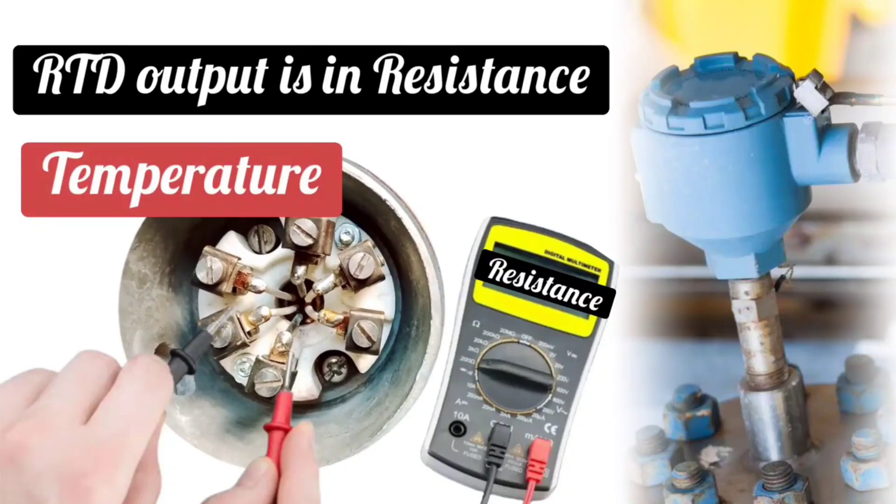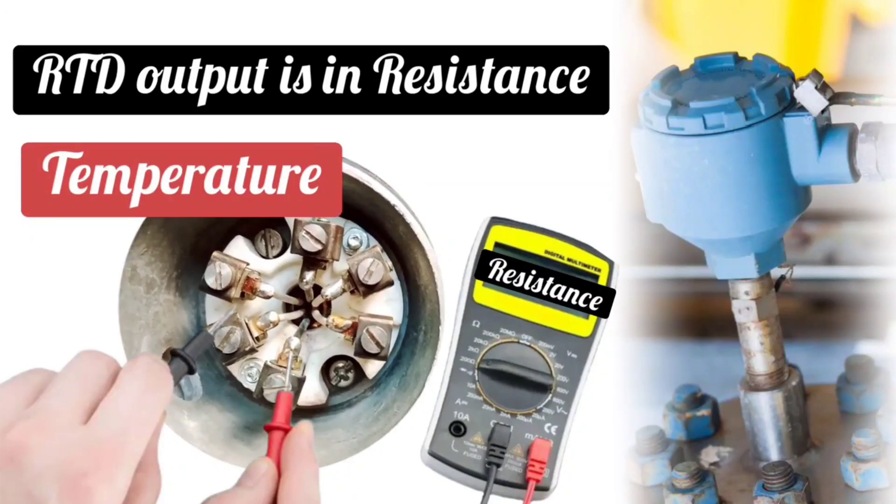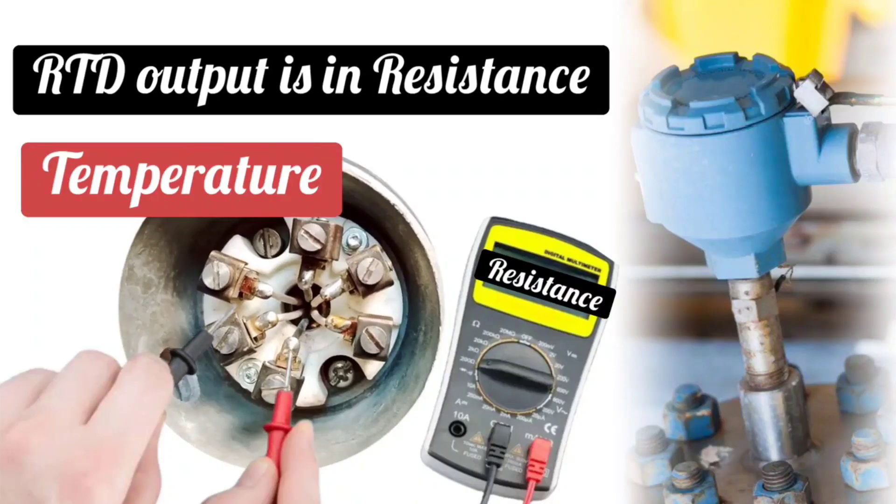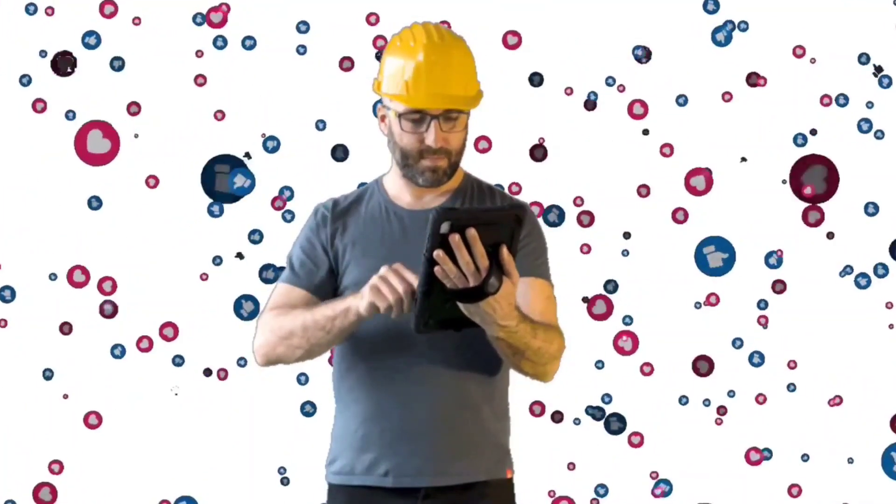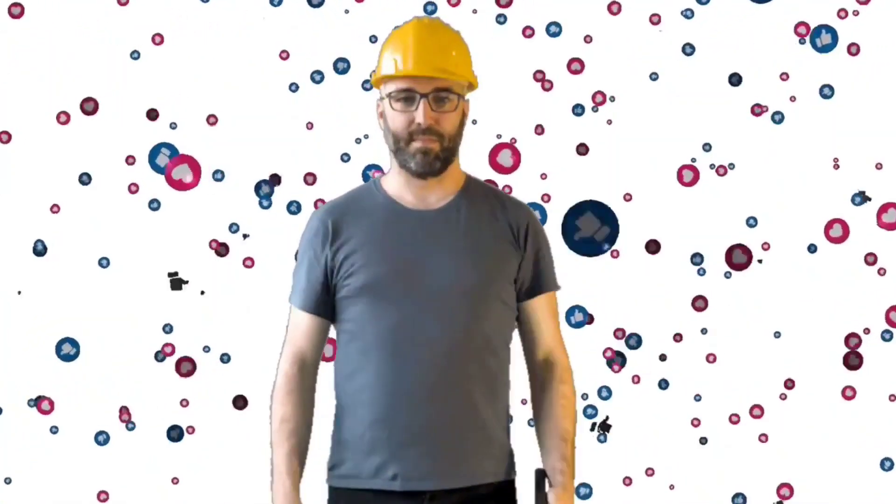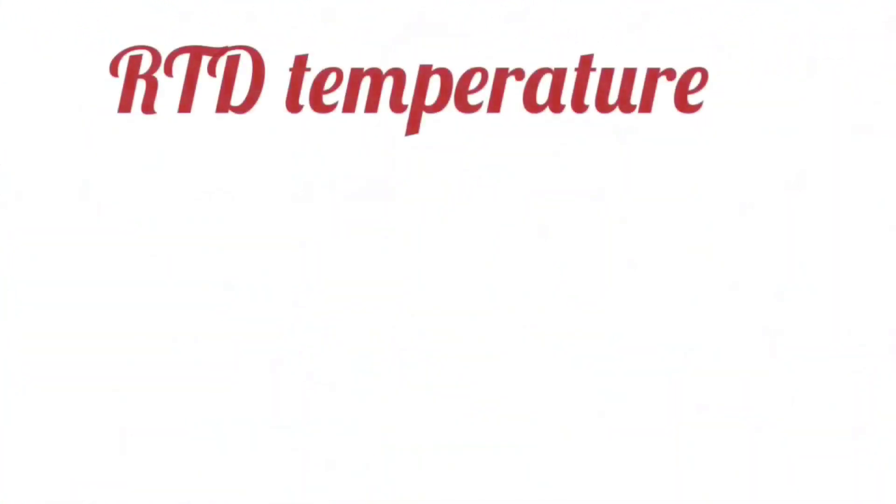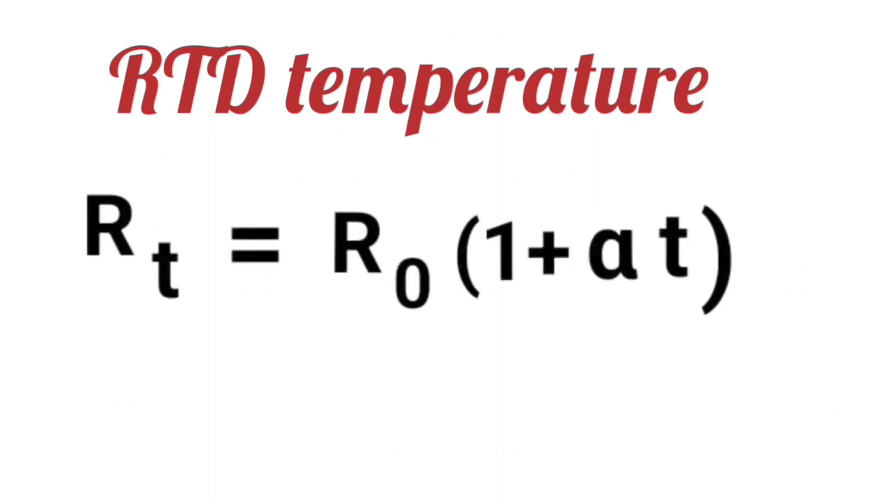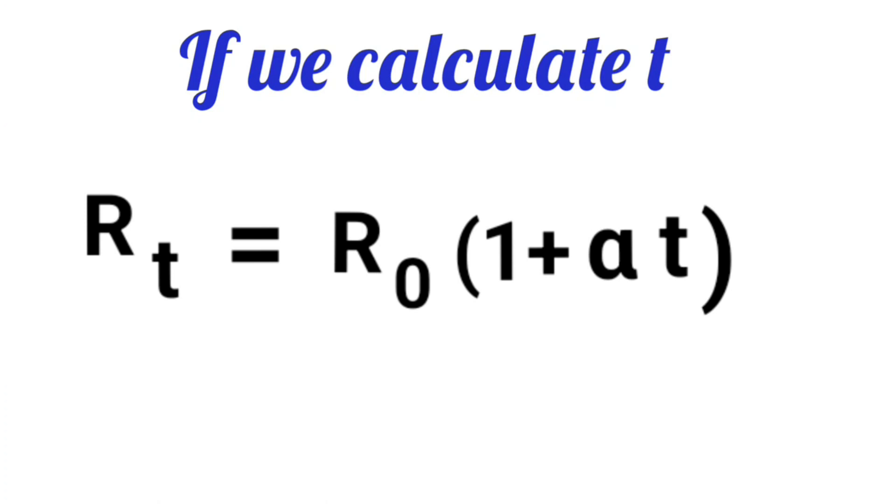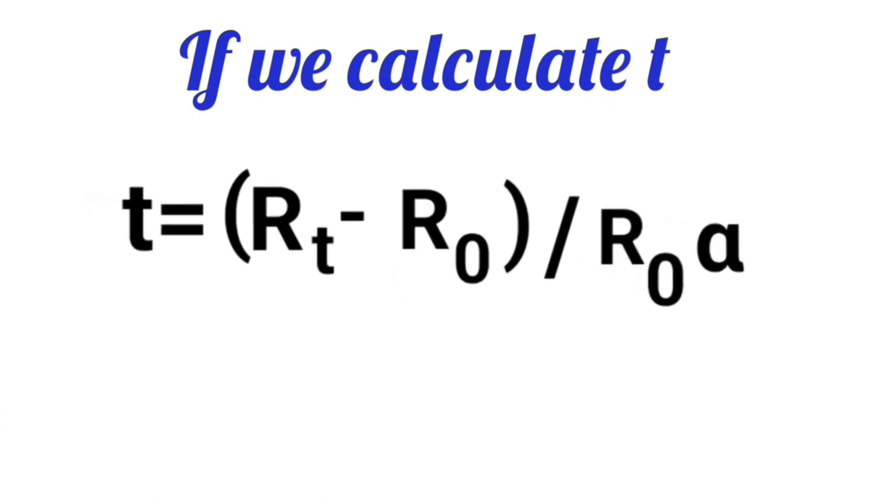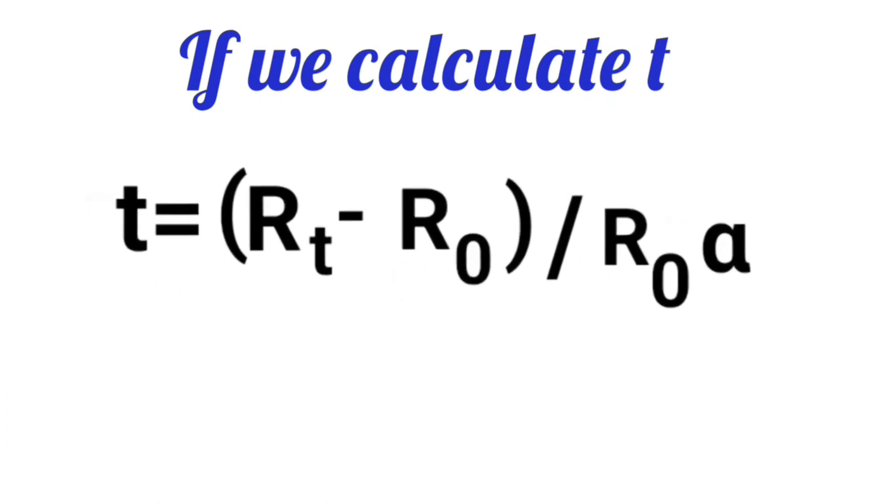Today we will see how the temperature of RTD is calculated from this resistance. Today I am going to tell such a trick by which you can take out the temperature of RTD in a pinch. Well friends, the temperature calculation formula of RTD is RT equals R0(1 plus alpha T). If T means temperature is calculated from here, then it will become T equals (RT minus R0) divided by (R0 alpha).